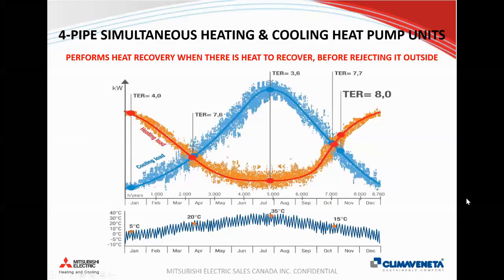And typically you'll have the highest total efficiency ratio whenever your loads are balanced. So whenever your heating and cooling loads are matched, basically you're not using your condenser coils or fans on the machine, and you're just doing internal heat recovery within the machine and getting higher overall efficiencies. But again, it's proportional to the load profile for the building.